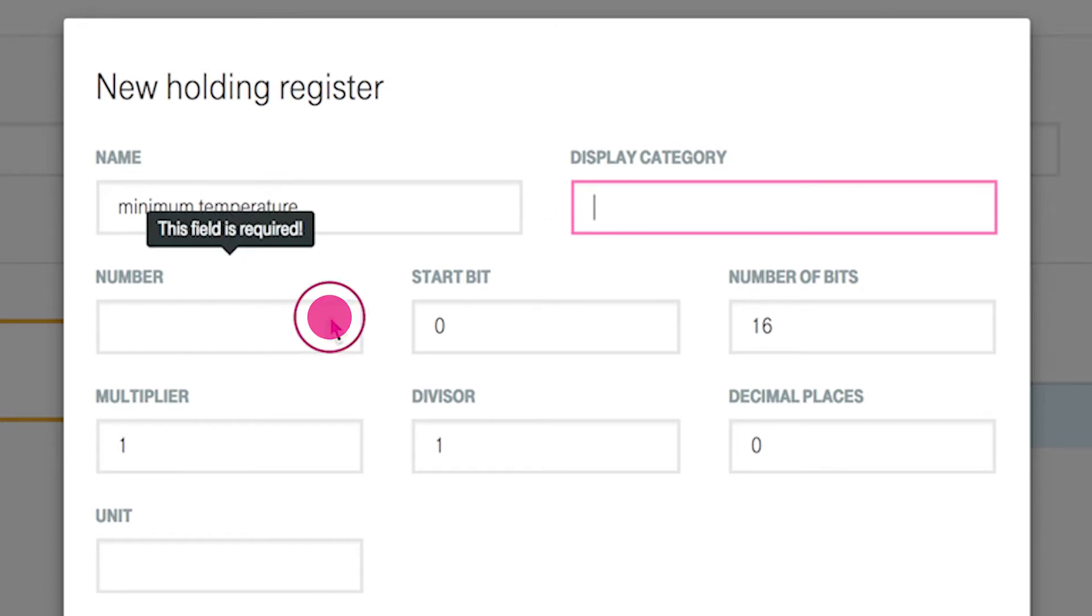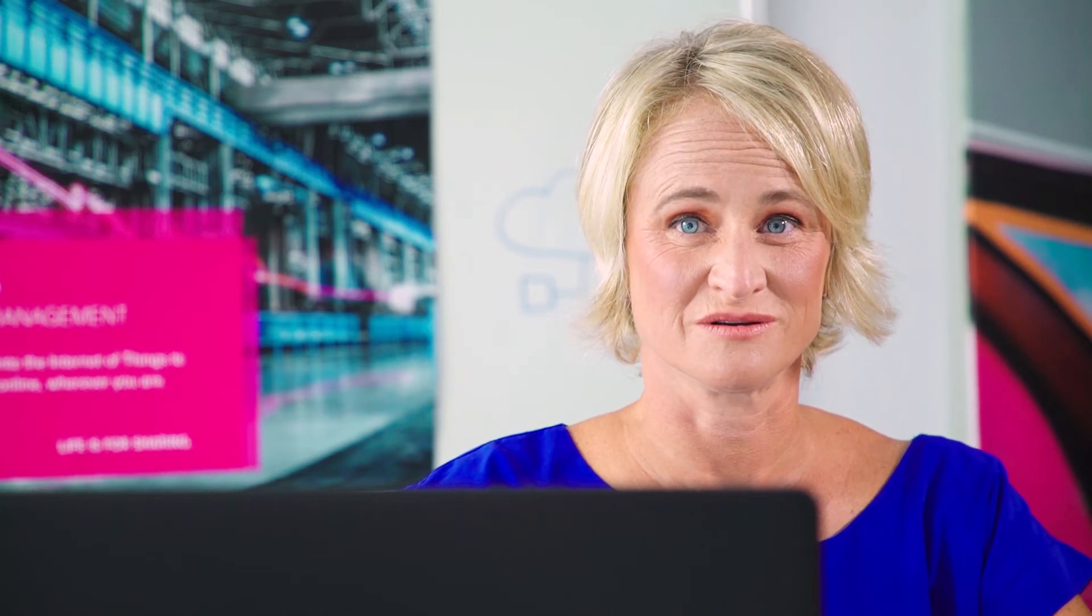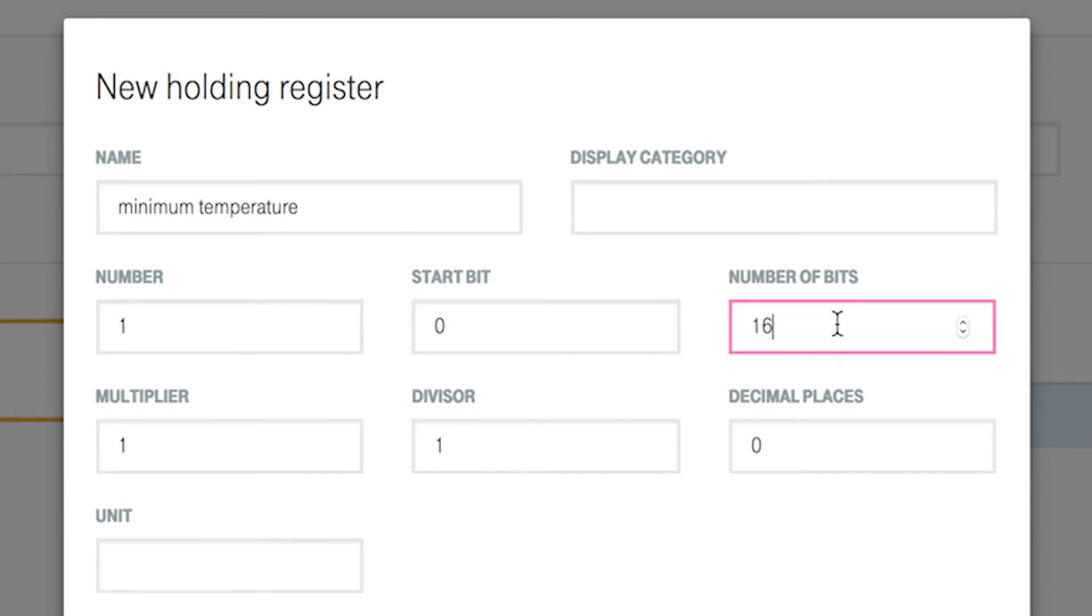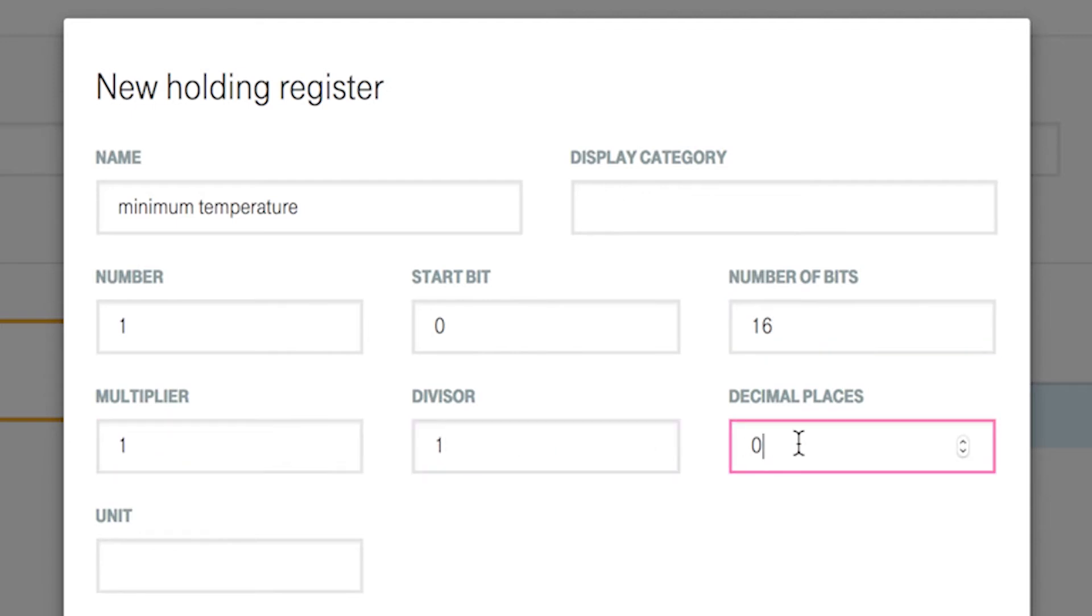You define the start bit and the register width according to the device description. Use start bit 0 and number of bits 16. By usage of the field multiplier, divisor or decimal places, you can format the raw data from the Modbus for your intended usage. In this example case, we use the given defaults.